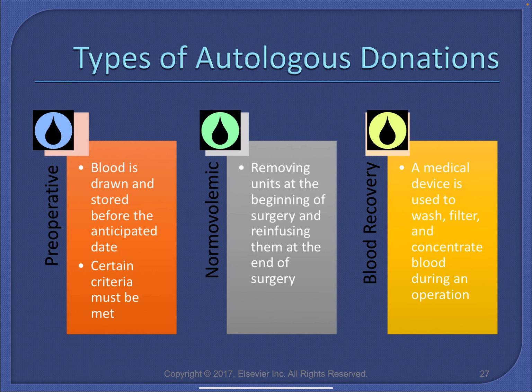And lastly, the blood recovery collection is when blood is being recovered and reinfused. So this is the collection and the reinfusion of shed blood. So there is a medical device that collects shed blood from an operative field, and they collect it and then directly reinfuse the blood using this device. The device will wash the blood, will filter it, and it will concentrate it. Now, just because we're doing this, it doesn't necessarily mean that it's removing bacteria. So intraoperative blood collection is not advisable if the operative field has bacterial contamination, because that would put the patient at risk.